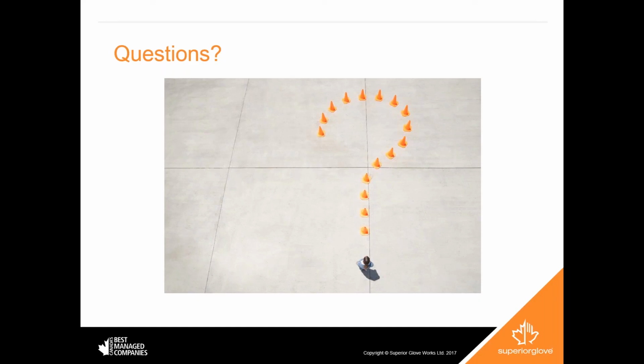We've also had a question here about the construction of the gloves themselves, so what kind of fabrics they're being made out of, whether they're a Kevlar, just what are the fabrics that are used in an arc flash glove? Most all your arc flash gloves today are being made of one primary material, which has to be flame retardant based. If we try and dumb this down, which was the whole purpose of this webinar today, think of it this way: you want to wear a glove, in our case what we're talking about, or this will hold true for your clothing that someone mentioned earlier, where the clothing or glove itself, the piece of PPE, will not cause any more damage to the person wearing it, i.e. it's not going to continue to burn, it's not going to melt on them.